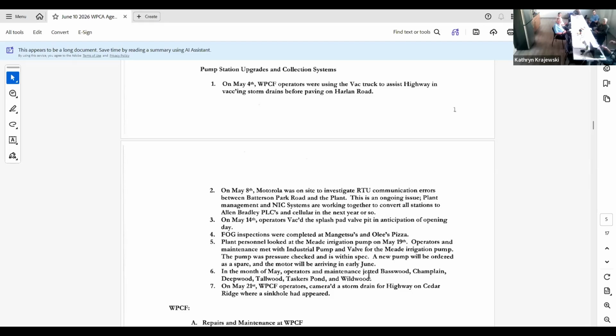NIC calibrated it, so there's a little PLC. When the splash pad opens for the day, it automatically opens, just like a valve. When it closes, it shuts off on a timer, and then it cycles the valves - we can set it to go once a day, twice a day, or once a month, just so that over the winter when it's not in use, the valves don't stick. It can also be weather-based, turning off automatically when it rains - the PLC can do pretty much whatever you want. For something this simple, we run it 7 to 7 or whatever the hours are, with different weekend hours, and from Labor Day to Memorial Day we exercise it twice a week so the valve doesn't get stuck. That was our responsibility. It's probably one of the nicest setups in the state for a splash pad, and we can access it on SCADA to change any of the parameters.